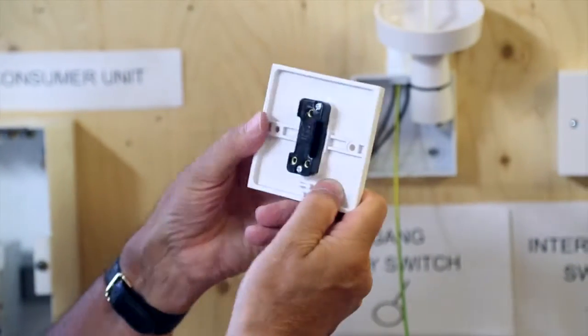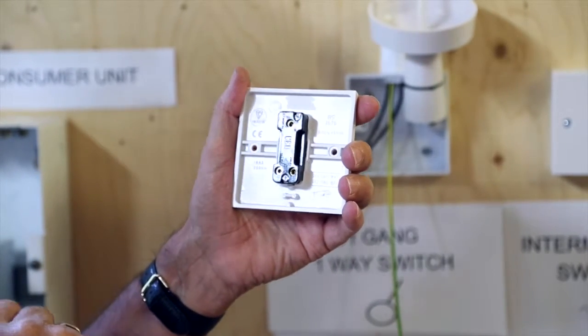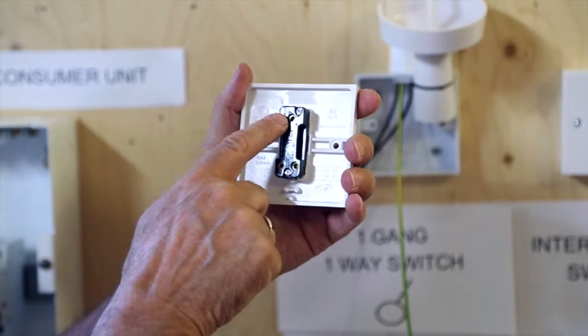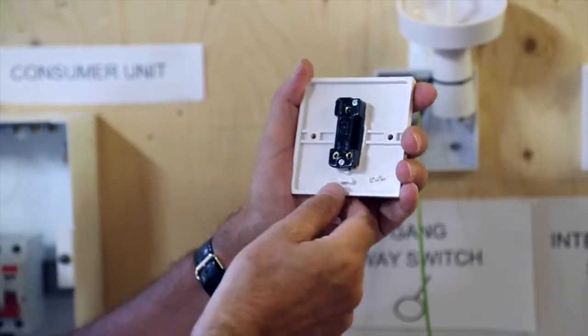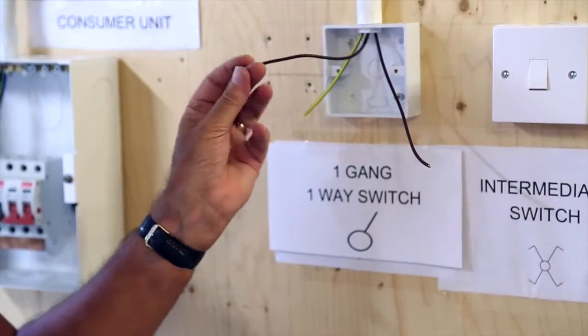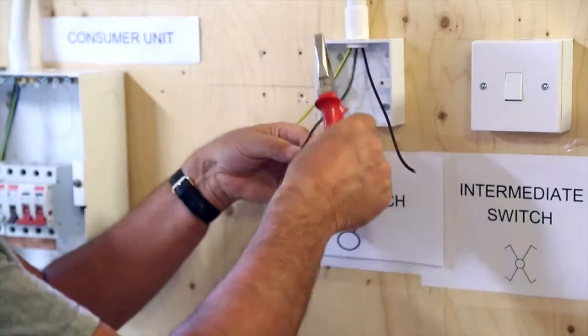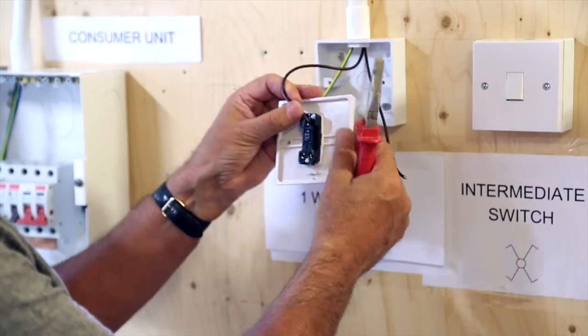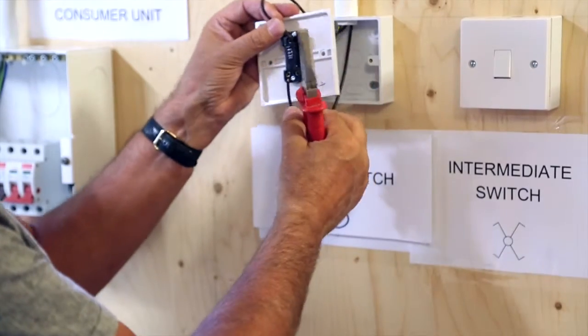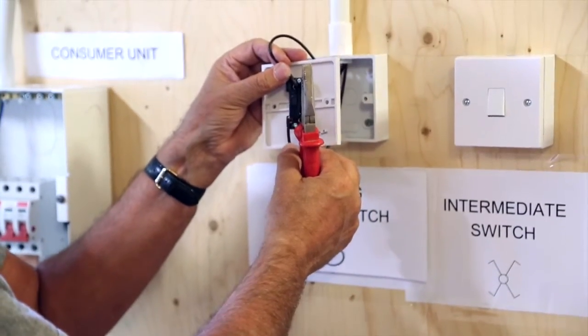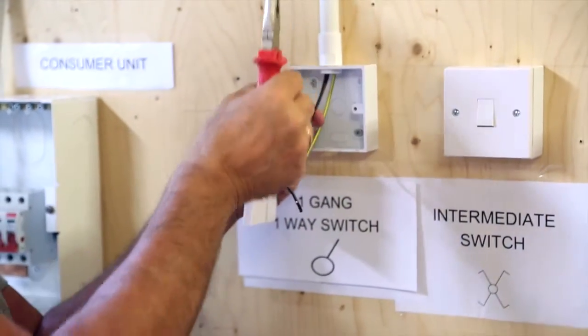The switch we use has the availability of one-way and two-way. For the one-way we'll be using the common and the bottom left hand termination here which is identified as one-way. This cable which I bent over is our feed from the consumer unit which will go into the common of the switch. And I will then proceed to connect the return to the ceiling rose into the one-way element of the switch. When cutting these cables don't cut them too short in case you need to get the face plate off. So give yourself a little bit of room for the cables itself.